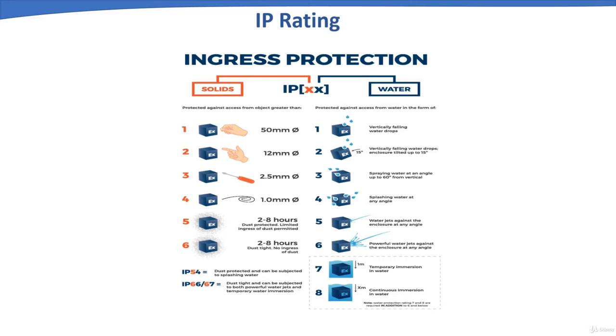The first number indicates protection against intrusion of solid foreign objects, and the second numeral indicates the degree of protection against moisture ingress. For example, an IP rating of IP67 means: the first numeral 6 indicates the object can withstand dust ingress for 2 to 8 hours and is dust-tight. The second numeral 7 means the object can be temporarily immersed in water up to 1 meter and remain protected.